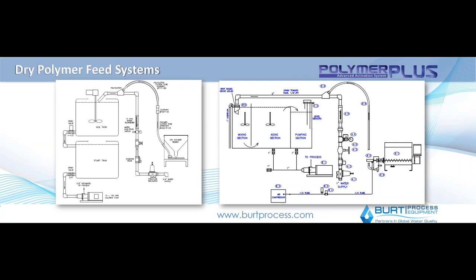So what's really the advantage of dry over liquid? The advantage of dry polymer is that you can store it for a lot longer. Liquid polymer tends to have a much shorter activated life, so you tend to buy as you need it. Whereas dry polymer, if kept in a humidity-controlled environment, allows you to store a lot more polymer on site. If you have an application where you need a lot more polymer, going with a dry polymer-based system can be very helpful. A liquid-based system has less equipment and is less costly to utilize, but you have to keep bringing in a liquid chemical. Some people also just prefer the safety handling of a dry polymer facility over a liquid polymer system.